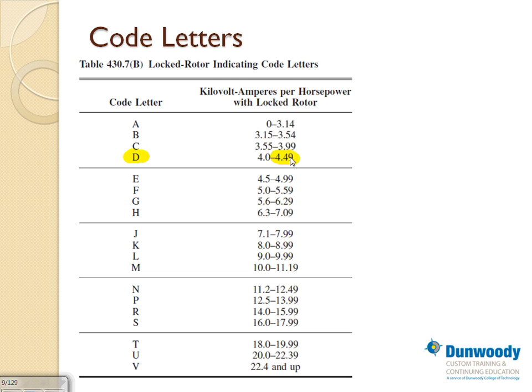A 100 amp motor, design code letter D, if it says code letter D on there, that can pull out of the system 449 amps for no more than 10 seconds. Again, the problem is 10 seconds is not a whole lot, but that's enough to screw up your system. Then the equipment affects the function of other equipment. So get used to this. When you do the calculation, it's a range. You always go to the upper limit because that's the worst scenario, right? Worst scenario is upper limit.